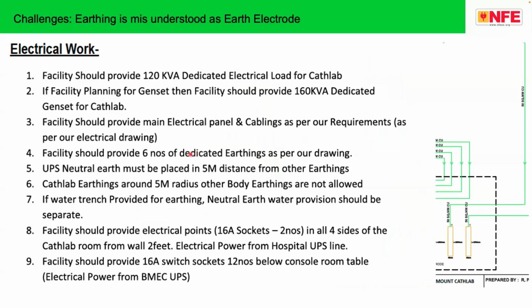Please note that these 6 numbers of dedicated earths are a big mistake. These earth electrodes are going to endanger your equipment as well as the patient and the doctors. UPS neutral earth must be placed 5-meter distance from other earthing. Cath lab earthing should be 5-meter radius. Other body earthings are not allowed. Serial number 7 was the most funny part.